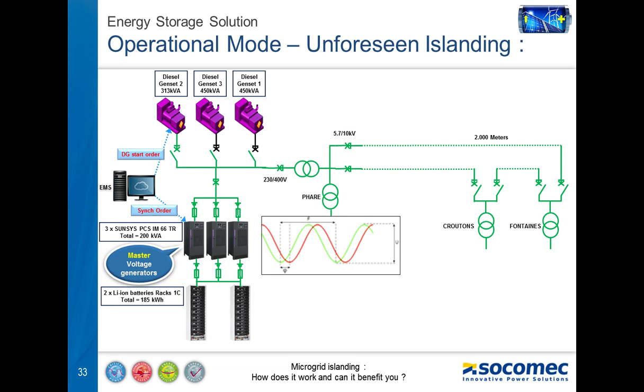From this situation, the genset is started. Once the nominal speed and voltage are reached, the EMS can ask for the synchronization sequence, either from the genset or from the PCS. The target of this sequence is, one more time, to ensure the perfect alignment between the three parameters, which are voltage, frequency, and phases.